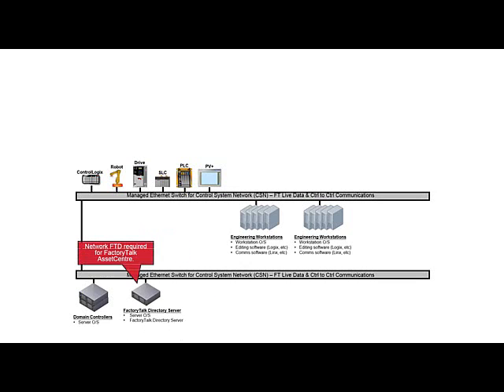With the domain in place, the next component to consider is the FactoryTalk Services Platform itself. Each FactoryTalk Asset Center system will require a network FactoryTalk Directory Server, commonly abbreviated as FTD. This is simply a host with the services platform installed that has been designated as the FactoryTalk lead for the rest of the application. Rockwell commonly recommends using an independent host for the FactoryTalk Directory Server, as shown here.